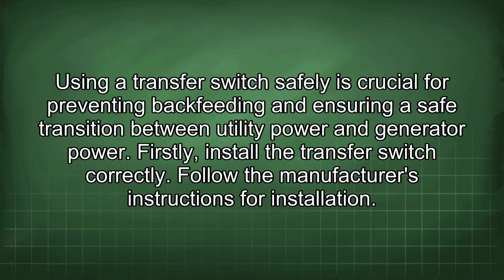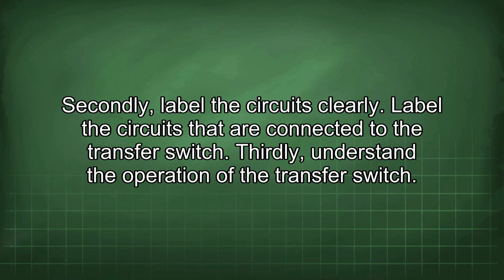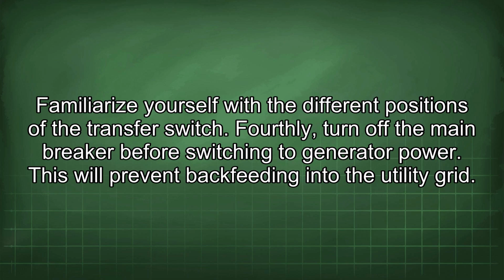Using a transfer switch safely is crucial for preventing backfeeding and ensuring a safe transition between utility power and generator power. Firstly, install the transfer switch correctly. Follow the manufacturer's instructions for installation. Secondly, label the circuits clearly. Label the circuits that are connected to the transfer switch. Thirdly, understand the operation of the transfer switch. Familiarize yourself with the different positions of the transfer switch.